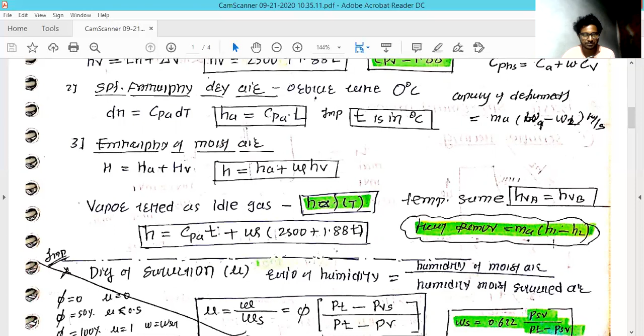Another formula is for finding the capacity of dehumidification, the amount of dehumidification taking place. It can be calculated as Ma into the difference between the specific humidity at the two stations. We take a similar example here, in which the mass flow rate through the pipe is the mass of air, and W1 and W2 are the respective specific humidity values at the two conditions. With these, we can find the amount of dehumidification.